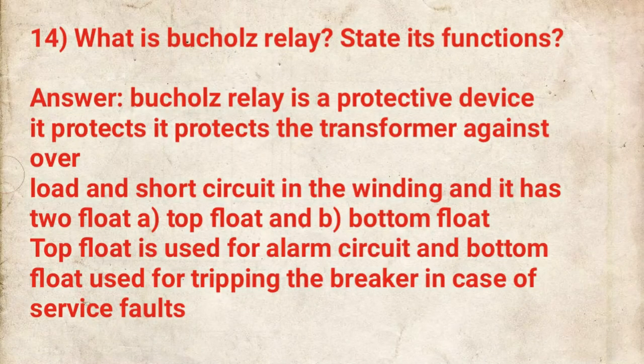What is a Buchholz relay? State its function. Buchholz relay is a protective device. It protects the transformer against overload and short circuit in the winding, and it has two floats, top float and bottom float. The top float is used for the alarm circuit and the bottom float is used for tripping the breaker in case of serious faults.